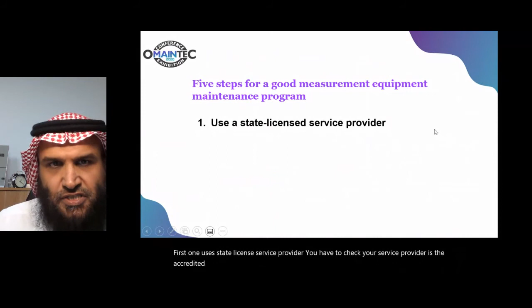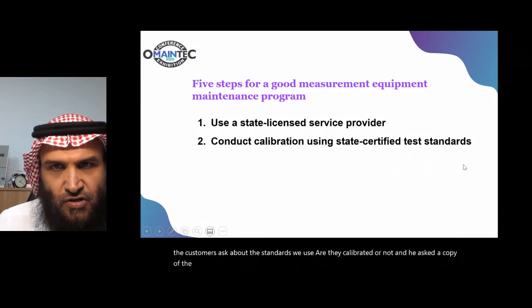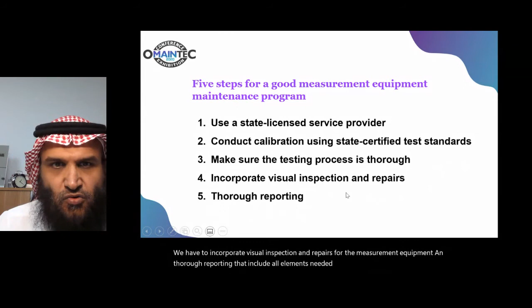First one, use a state licensed service provider. You have to check your service provider. Is he accredited? Is he licensed by the authority or not? Also, you have to conduct calibration using state certified test standards. You have to check also that the provider used the right standard. And we are very happy in GCC Lab when one of the customers asks about the standards we use. Are they calibrated or not? And he asked for a copy of the calibration certificate of our standards. We have to make sure the testing process is thorough, complete, and considers all parameters that impact the measurement process. We have to incorporate visual inspection and repairs for the measurement equipment, and thorough reporting that includes all elements needed to ensure that measurement equipment is operating properly.